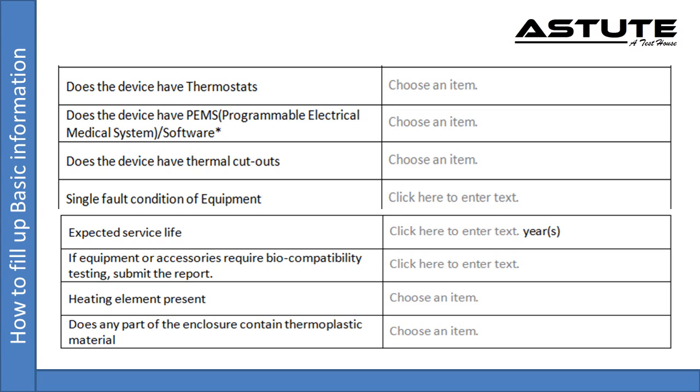Expected service life is the time period specified by the manufacturer during which the ME equipment or ME system is expected to remain safe for use. ME equipment, ME system, and their parts or accessories intended to come into direct or indirect contact with biological tissues, cells or body fluids shall be assessed and documented according to the guidance and principles given in the ISO 10993 series of standards.